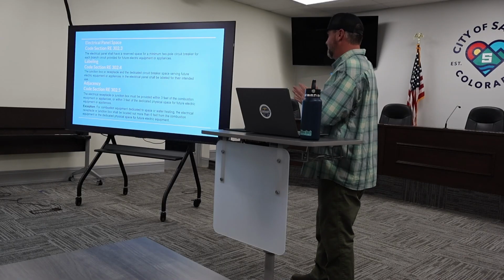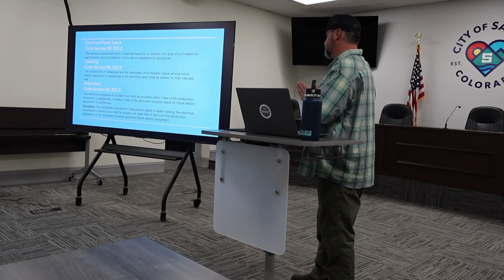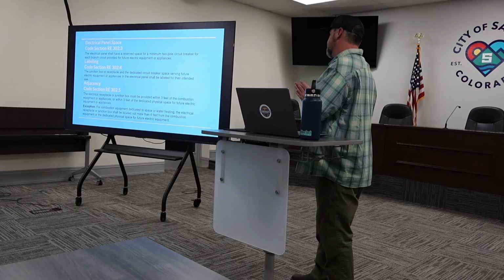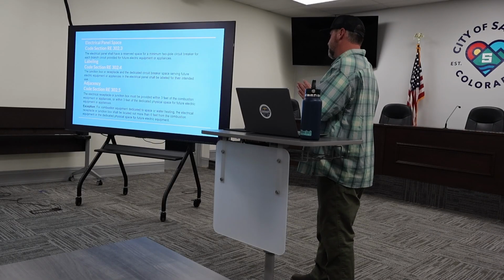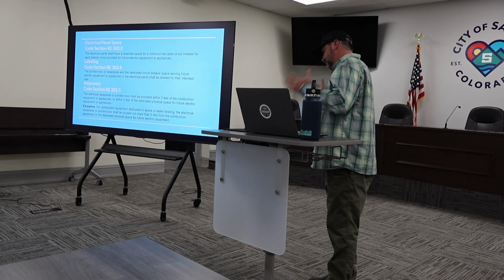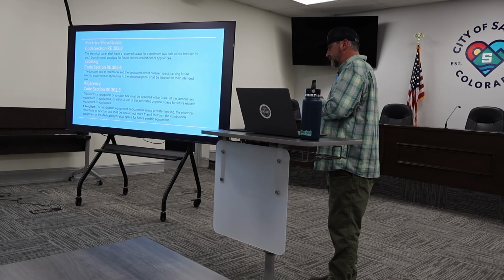And then this word, adjacency. The electrical receptacle or junction box must be provided within 3 feet of the combustion equipment or appliances, or within 3 feet of the dedicated physical space for future electric equipment or appliances. There's an exception for combustion equipment dedicated to space or water heating. The electrical receptacle or junction box shall be located not more than 6 feet from the combustion equipment or the dedicated physical space for future electric equipment. So yeah, again, it's taking into account that dedicated space and where that is. That's why sometimes a raceway makes more sense to me as well. So that's kind of what we've been doing with that.